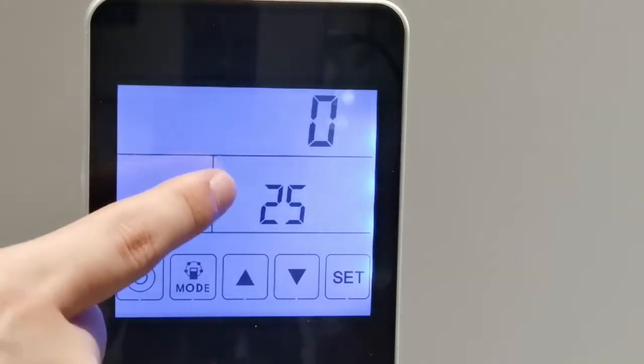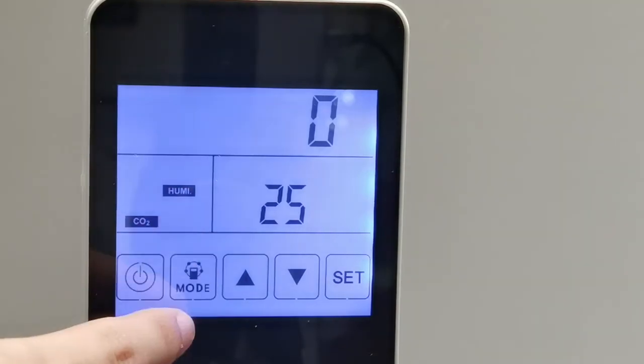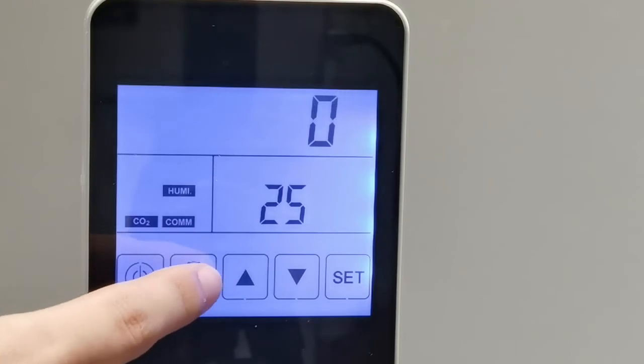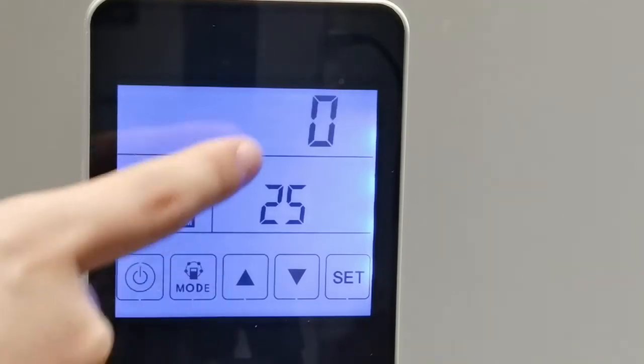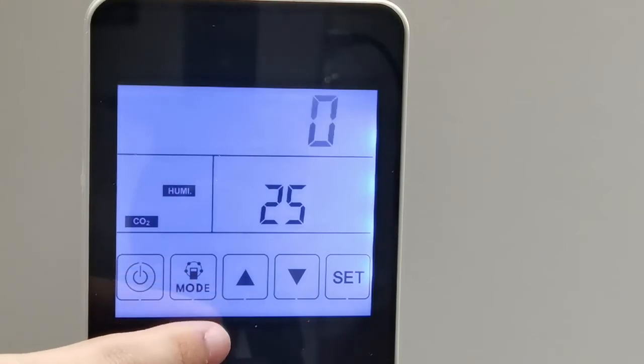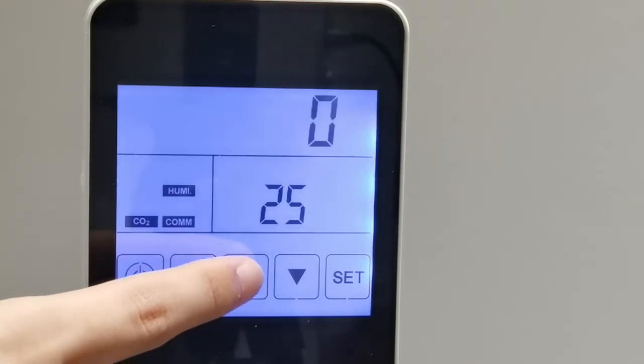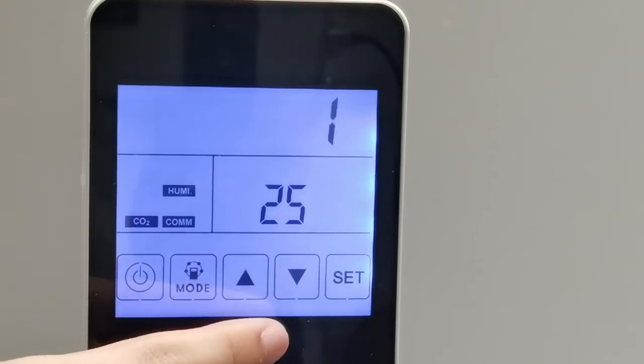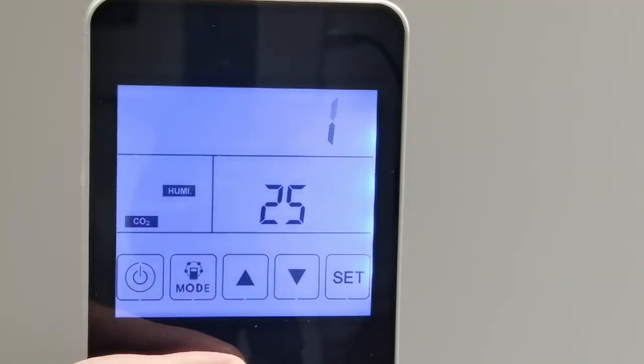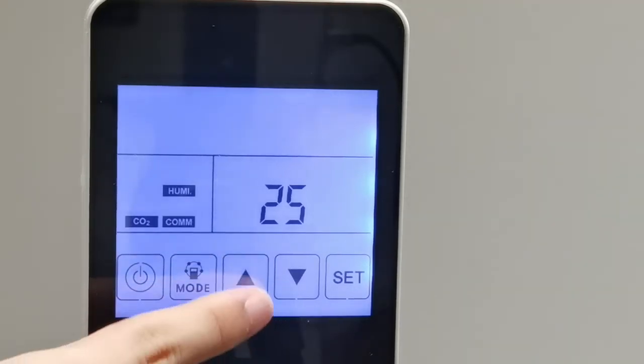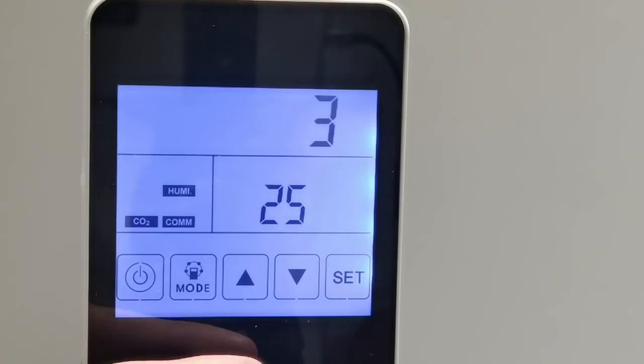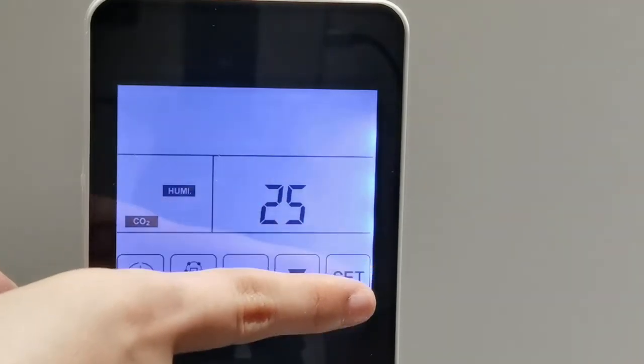And one more time. Let's move into parameter 25. It means the filter alarm setting. For example, if we want to change the filter every 45 days, we can select the value 0, and this is the default value. If we select 1 with the up button, it means 60 days. The number 2 means 90 days, and the number 3 means 180 days. Okay? Please remember the default value is 0. It means 45 days.